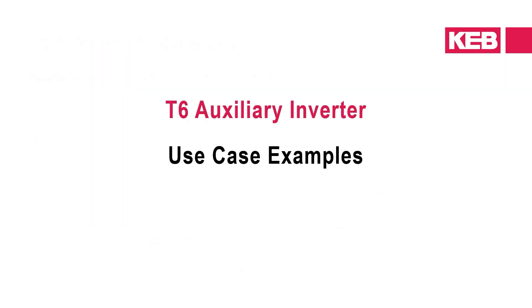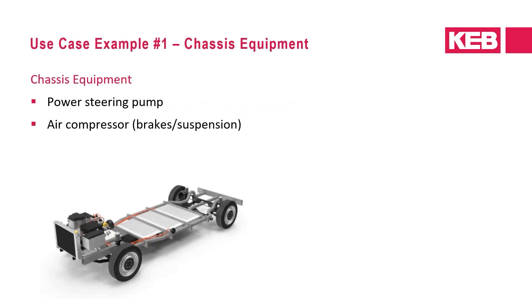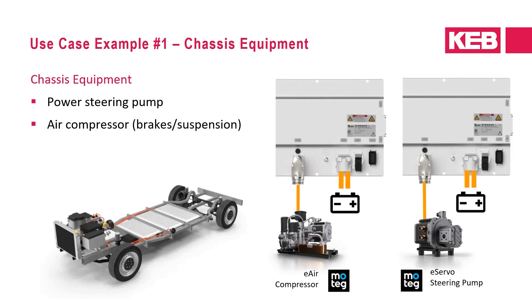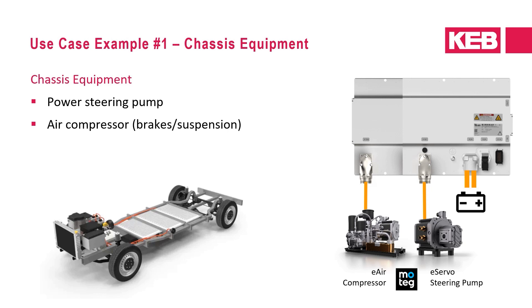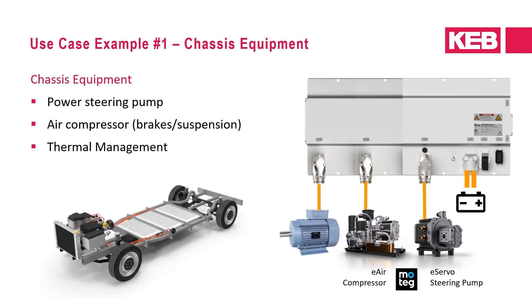With an overview of the T6 auxiliary inverter system in mind, I'd like to provide some use case examples, starting with the typical application. The most common applications start with electrifying chassis auxiliaries, including the power steering pump and air compressor for brakes and suspension. These components can be electrified each with their own inverter, or more preferably combined into a two-in-one system and independently controlled. The chassis equipment may also include thermal management such as a coolant pump or heat exchanger, extending the system to a three-in-one configuration.